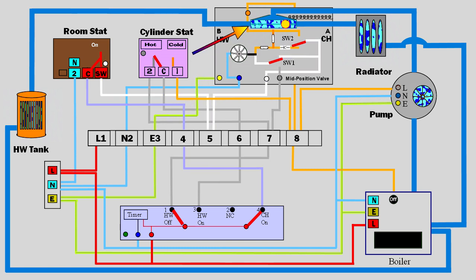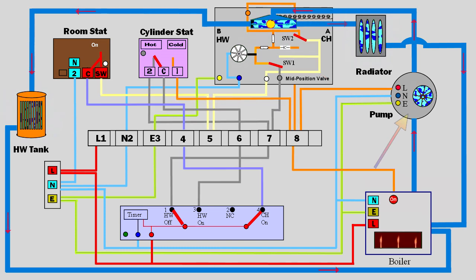The motor moves the valve to block the hot water exit. At the mid valve position, SW1 always changes over just ahead of SW2. SW2 starts the circulation pump and boiler.